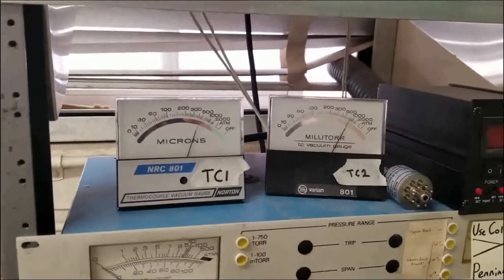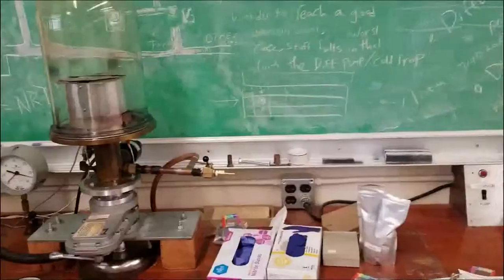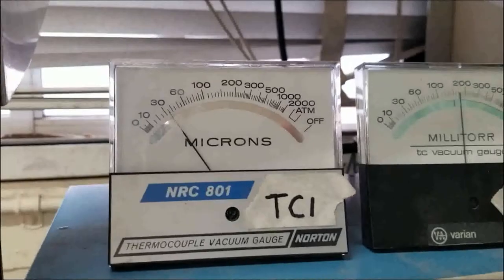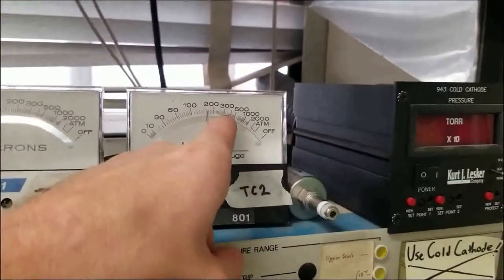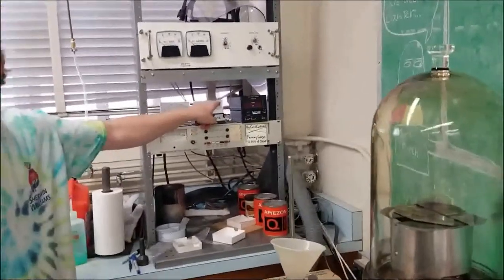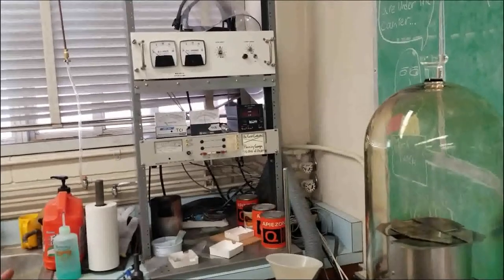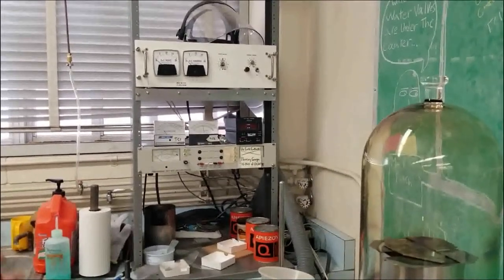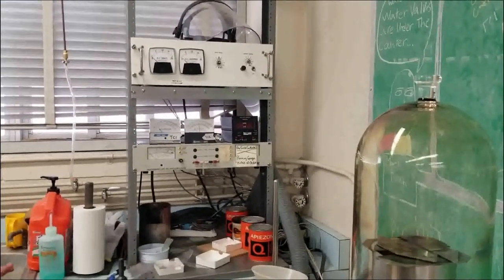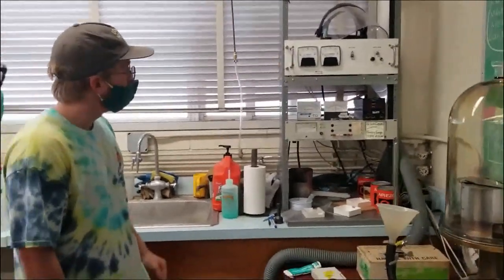Then you should start to worry about if the students can complete the experiment. So this is actually already down low enough. I just use this as a judgment and just say never go above 300. Above 300 is bad. And when bad things are happening, like when oil is actually shooting up into this thing, it won't just go to 300, it'll get to 1000. So you won't really be able to miss if something's going wrong. And if something goes wrong it will probably still work. You probably won't even need to clean it. You'll probably need to clean it if you mess it up like three or four times.